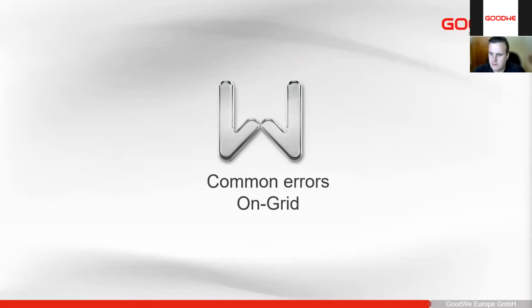Now in the poll, we continue. We do have a question. When we have no battery, can a smart meter test be done because the BMS communication has failed? So we do have an option for no battery in our battery selection. If you select the no battery option, then the smart meter test should work correctly because it should already pick up that there is no battery. If you don't have the option, it could perhaps mean that the firmware of the inverter is a bit older and it doesn't have that option available.